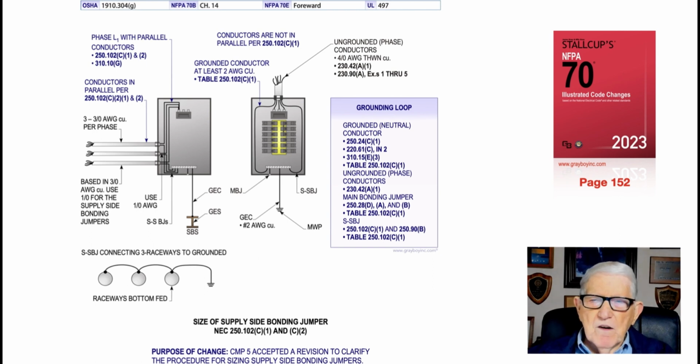Now down at the very bottom of the illustration, we have 3 conduits entering from the bottom, and they have 3/0 AWG conductors also in each raceway, and we're using 1 conductor to serve all of those to ground. So we go to Table 8, Chapter 9, and a 3/0 AWG is basically 167,800 circular mil.